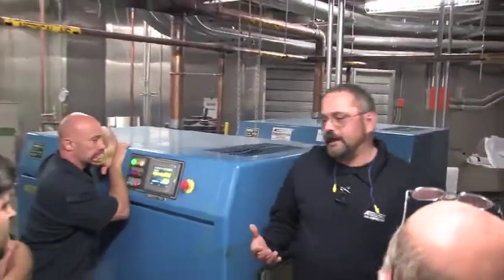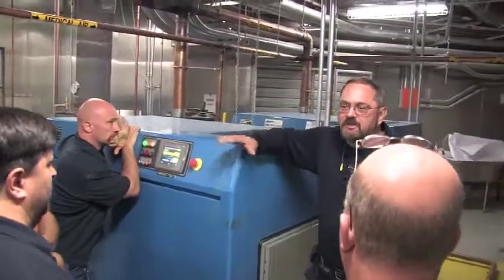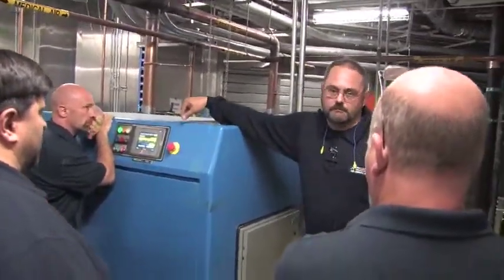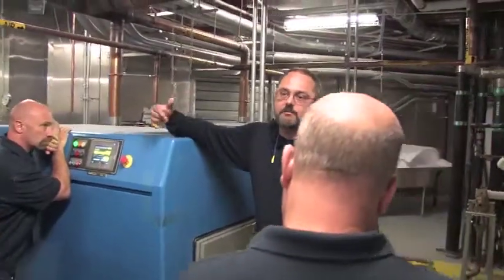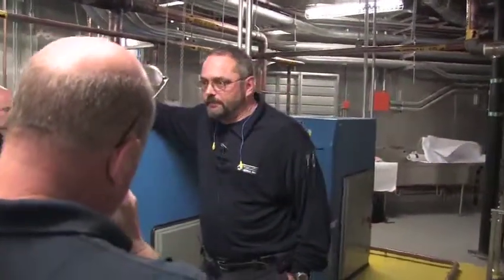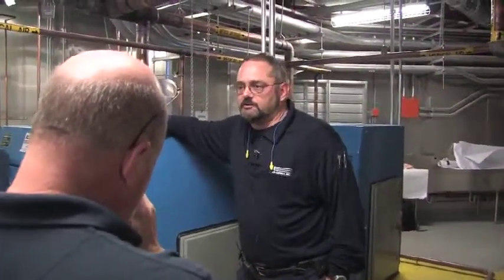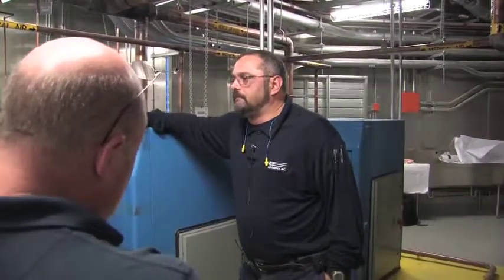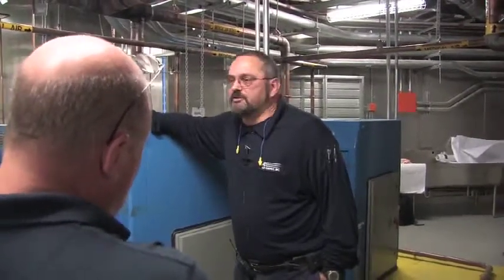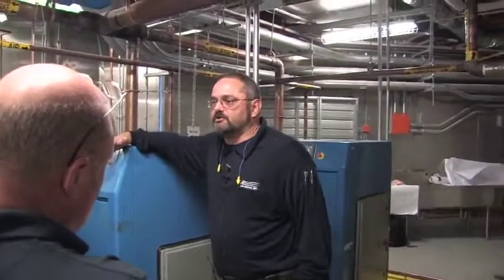Now here's the important thing. That lag means nothing if you're in remote. It's an artifact because these are sort of double programmed. And the reason for the double program in those, we can actually turn off the whole lead lag local system that's built into the unit controls and just put it in remote, where it'll just do whatever the sequencer tells them. The flip side of that is, if the sequencer crashes, it just reverts to whatever we have set into each one as a local control.